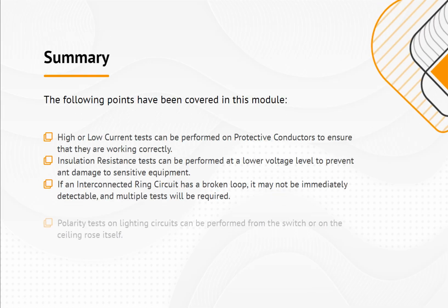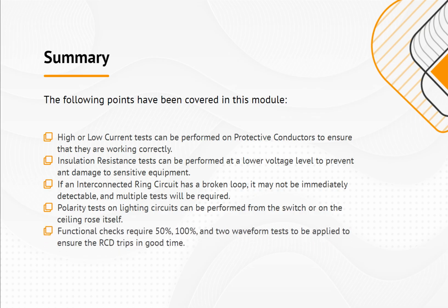Summary. The following points have been covered in this module. High or low current tests can be performed on protective conductors to ensure that they are working correctly. Insulation resistance tests can be performed at a lower voltage level to prevent damage to sensitive equipment. If an interconnected ring circuit has a broken loop, it may not be immediately detectable, and multiple tests will be required. Polarity tests on lighting circuits can be performed from the switch or on the ceiling rose itself. Functional checks require 50%, 100%, and two waveform tests to be applied to ensure the RCD trips in good time.